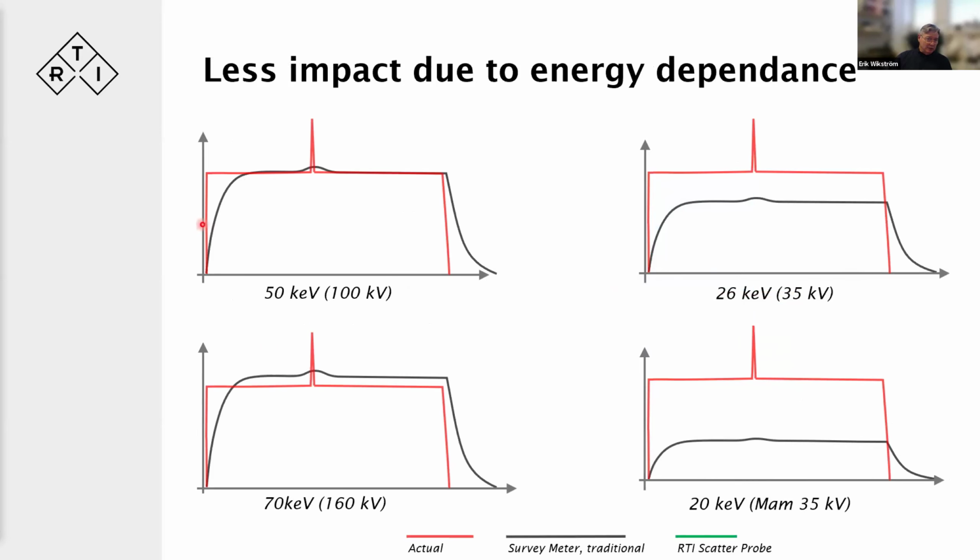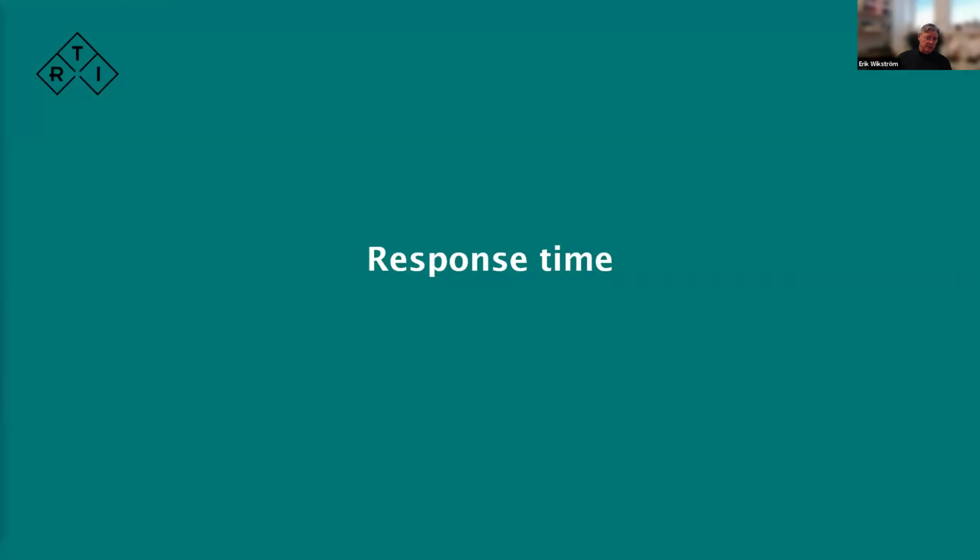Well, we saw these curves first, and here you see a better response time, so we track it more easily. Even if there is a bump in the road, we can monitor that and come up to the right value. Same thing here. It matches all along the waveform for all energies in the diagnostic imaging range.